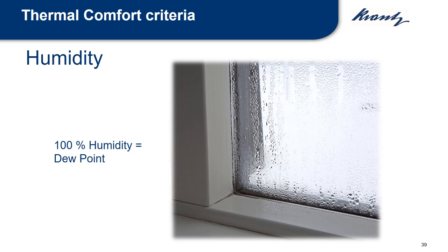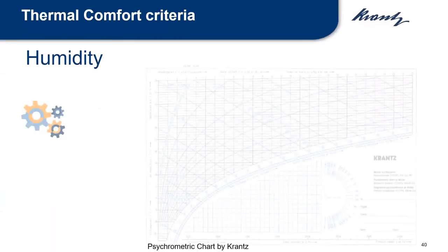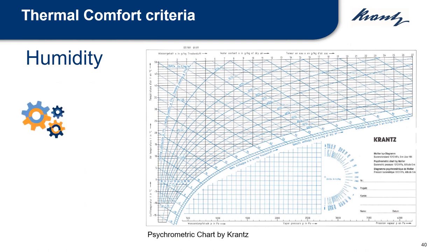Humidity. When we talk about humidity, we mean the relative humidity, RH, which is the ratio between how much moisture the air contains and the maximum amount that the air could hold at a given temperature and pressure. Warmer air can hold more moisture. When you approach 100% humidity, the air moisture condenses. This is called the dew point. We can obtain this information from a psychrometric chart, see table. The psychrometric chart is an important tool for HVAC engineers to carry out heat load or cooling load calculations and to find solutions to various air conditioning-related problems. We will cover this in more detail in further presentations.